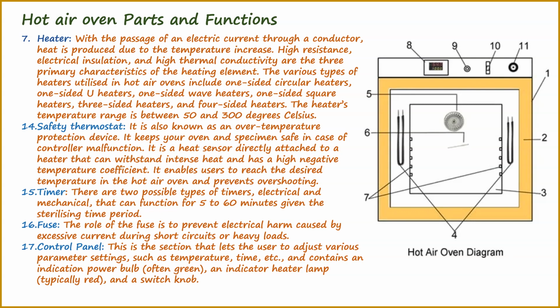14th part is safety thermostat. It is also known as an over-temperature protection device. It keeps your oven and specimen safe in case of controller malfunction. It is a heat sensor directly attached to a heater that can withstand intense heat and has a high negative temperature coefficient. It enables users to reach the desired temperature in the hot air oven and prevents overshooting.